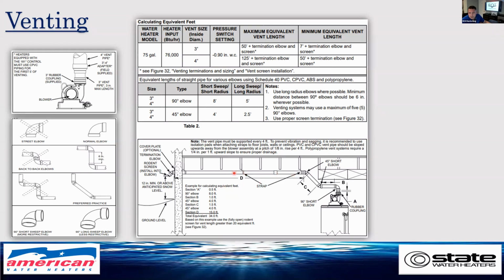Obviously, we want to add our strappings and support so we don't have sags and bellies inside the venting pipe. In here, this supplied 45 that comes with the unit, the reason why we want a 45 and not a 90 here is because we don't want combustion gases and hot air to be trapped inside this venting pipe, causing it to melt or the heater to overheat as well. So with a 45 on the end of it, we're allowed to exit our exhaust freely without the fan blowing as well. We don't trap it.